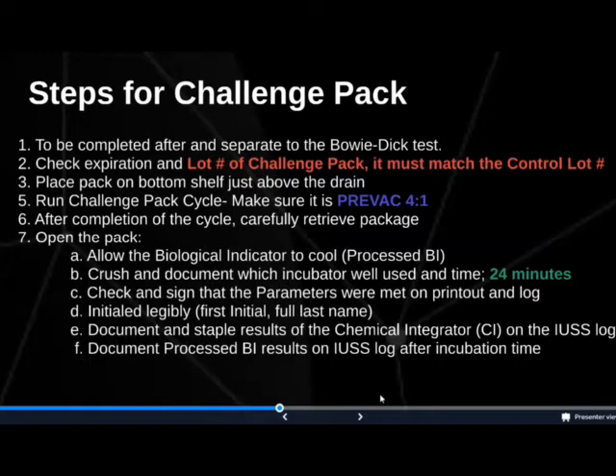This is your process BI, and we'll go over the log in just a bit. You're going to crush it, document the incubator well used and the time. And it takes 24 minutes for the incubator to read whether it is positive or negative. Check and sign that the parameters were met on the printout and the log. Initial legibly, always use your first initial and your full last name. Document and staple results of the chemical integrator, CI, on the IUSS log, and then document your process BI, the one that you just ran, results on the IUSS log after the incubation time, which again was 24 minutes.